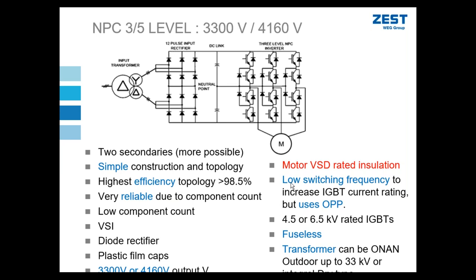One advantage is that it has a low switching frequency because of a concept called optimal pulse pattern. Optimal pulse pattern is basically a step above space vector modulation. In other words, it's even a better switching technique than space vector modulation. We'll cover that in some broad strokes later. This topology uses 6.5 kV rated IGBTs. We always want a safety margin between the voltage that we're switching and the actual rating of the IGBTs.